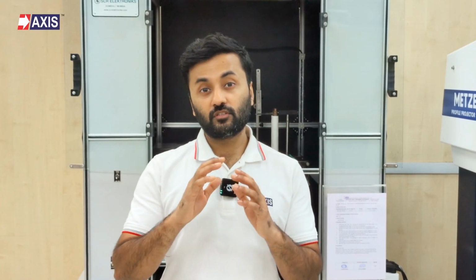If you're working in low voltage, the electrical stress on insulation is low. In medium and high voltage, it increases. The higher the voltage, the higher the stress on the insulation surface. Hence, you cannot use the same tubing or kit across all voltage levels. Then you should check the wall thickness of the material. Wall thickness means the thickness of the heat shrink after it fully shrinks onto the cable. It directly affects how much insulation distance you get between the live conductor and the outer surface. If the thickness is too low for your voltage level, the electrical stress becomes high across a small insulation distance. The material won't withstand that stress, leading to cracks in the insulation. This will lead to partial discharge, flashover, or complete failure.